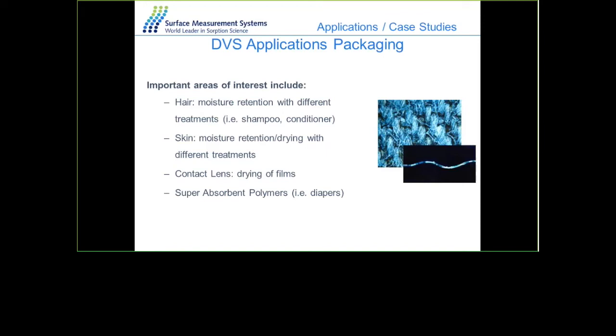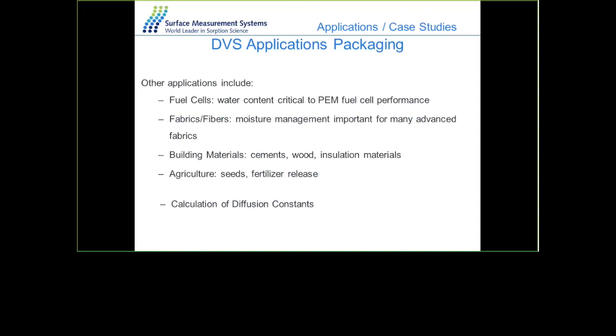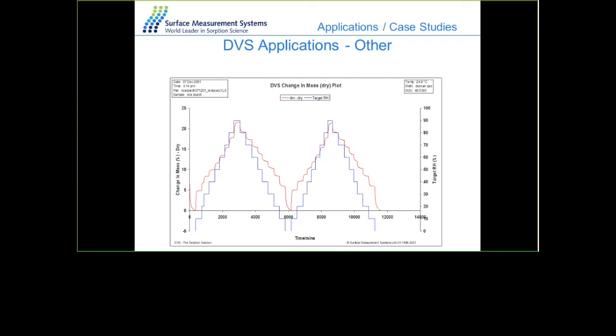For packaging materials, electronic components, blister packs, and listed packaging materials can be placed in the sample chamber as they come, and the diffusion and permeability of vapor through the packaging can be measured. Other applications include fuel cells and proton exchange membranes, fabrics and fibers, the interaction between fragrances and fabrics, washing powders, building materials such as cements, wood and insulation, agriculture including pesticides, seeds and fertilizer release — all with applications in DVS.